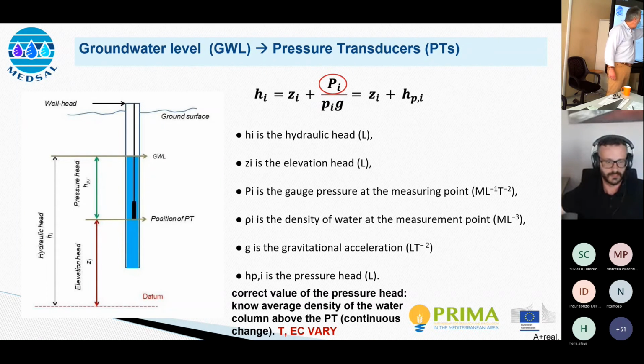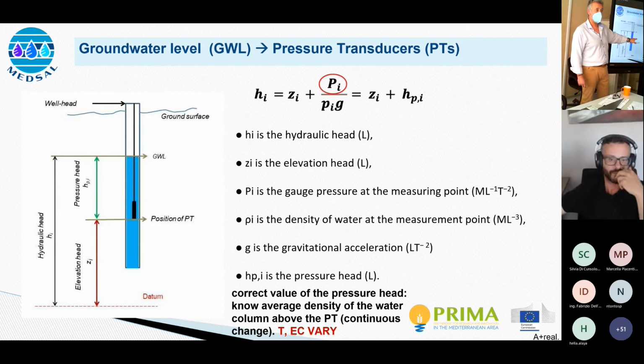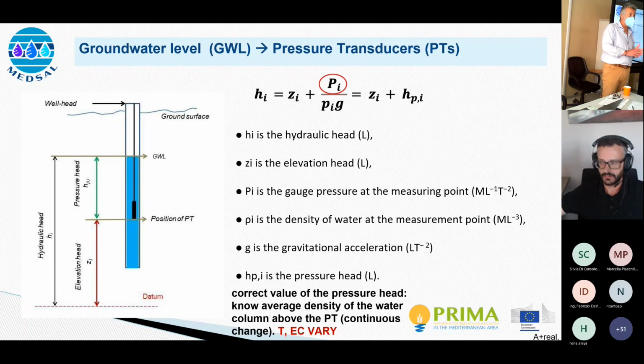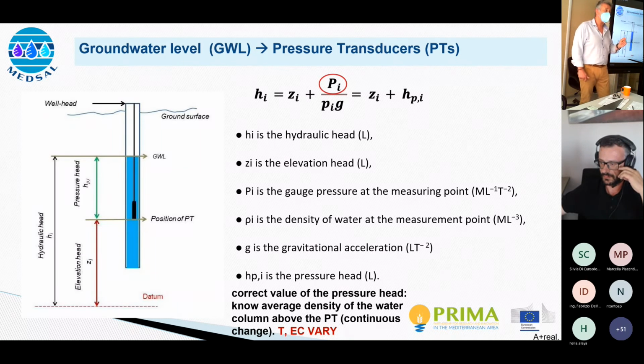So it will make all the difference in the world if this is salt water or fresh water, simply because fresh water has an average density of 1 gram per cubic centimeter. Okay, one, and salt water is 1.025 or less. Okay, so imagine how big a difference it makes. But this cannot be distinguished by the sensor. The sensor just measures pressure. Pressure is the result of the column and the density of the fluid. So you always need to compensate for the density in order to be sure what you're measuring.